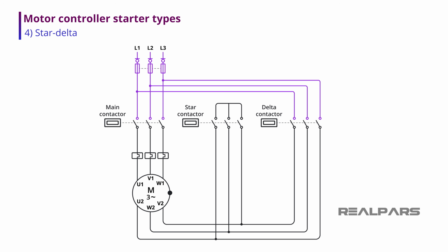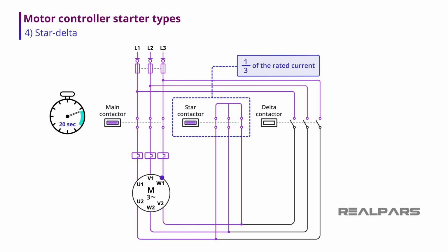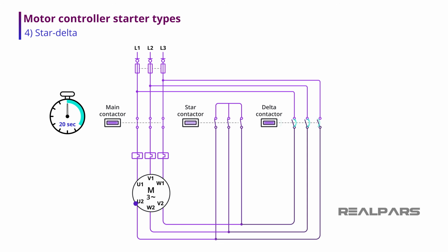Star delta reduced voltage motor starting is related to auto transformer starting, in that three separate contactors are used in the motor control scheme. In star delta, the motor is started in the star configuration, which starts the motor at about 1/3 of the rated full motor current. After the motor spins up to near full speed, the motor is switched to the delta configuration for continuous running.